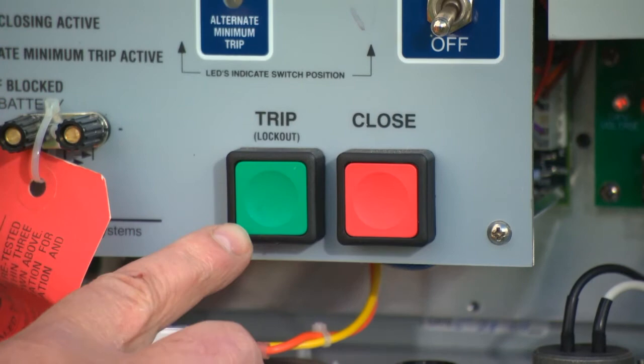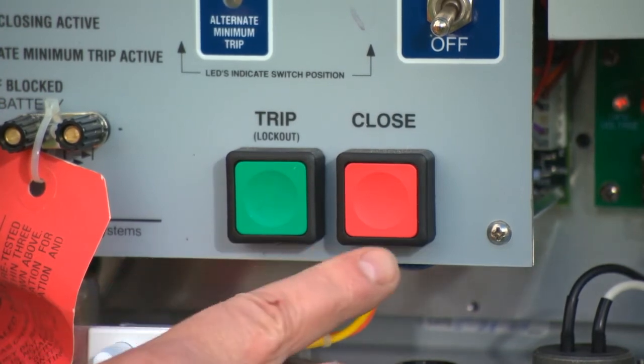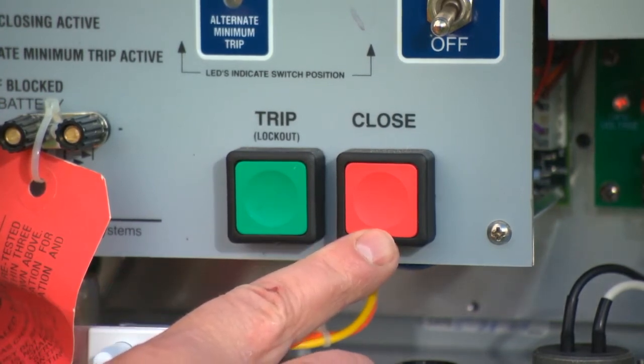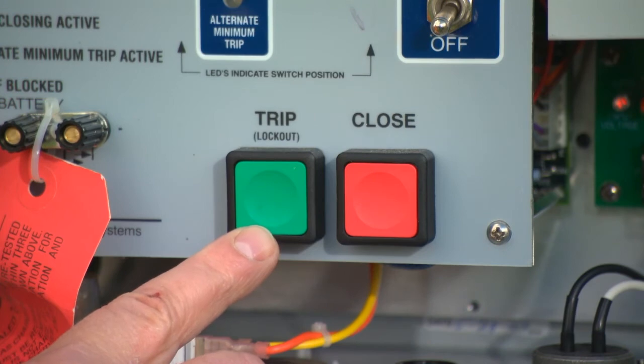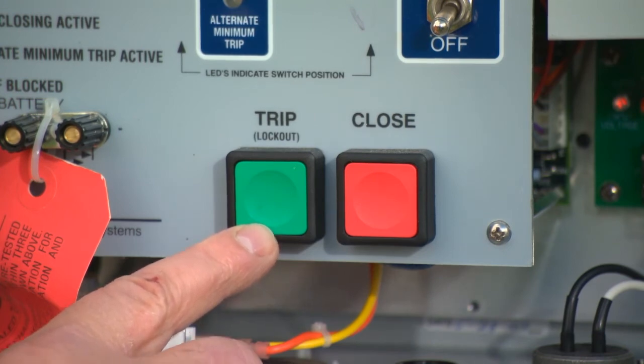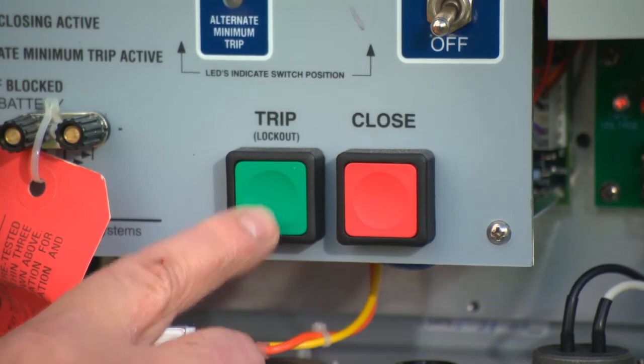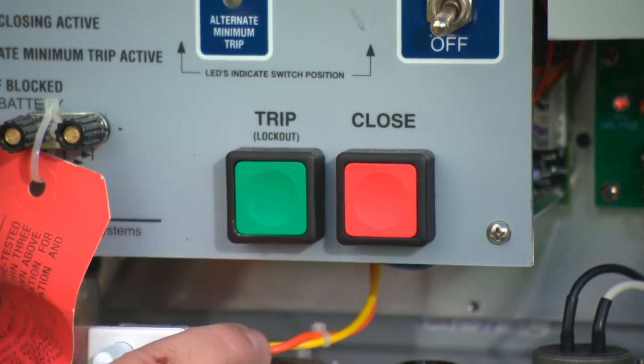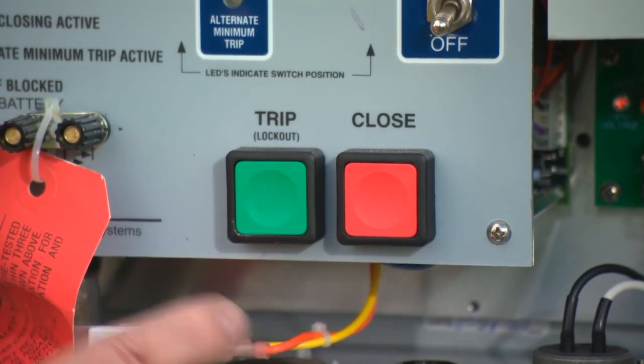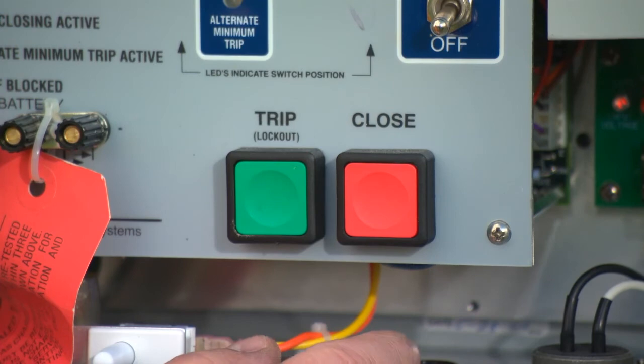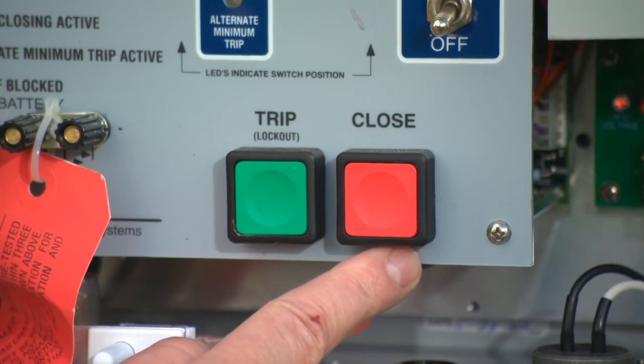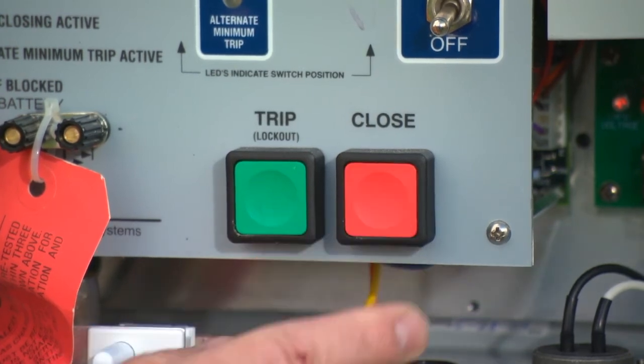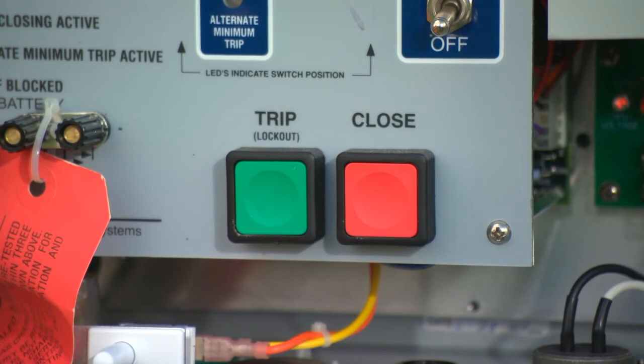Looking more closely on the bottom of the unit are the green trip and red close buttons. Since this is a gang-operated unit, applying the trip button will actively trip out all 3 phases. The phase indicator LED will signal a status change. After pressing the close button, you will notice that all 3 phases have closed, as indicated by the recloser closed LED on the left side of the panel.